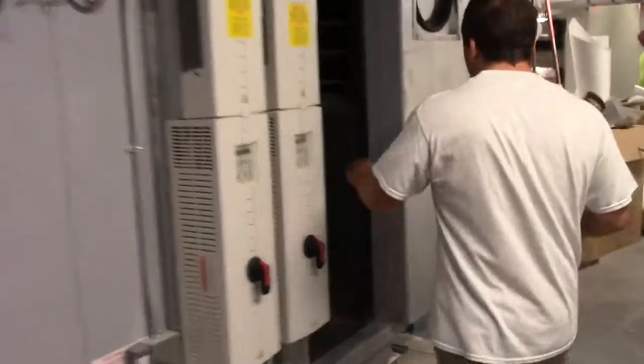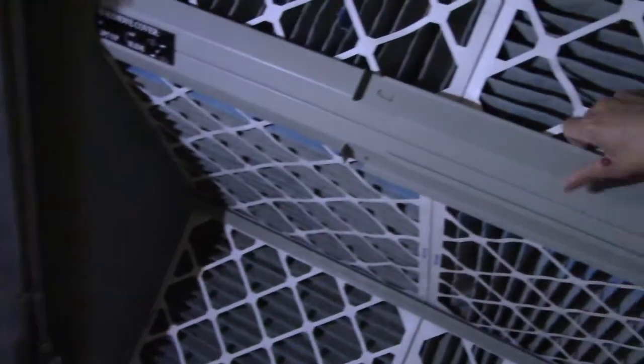There's a grease fitting on the heat wheel too. So you grease the bearing on that occasionally. Wait till you get in. This is the opposite side of the filters, obviously. You can either change them from this side or the other side. Probably easier to do it from here. It tells you how to remove the cover right there.